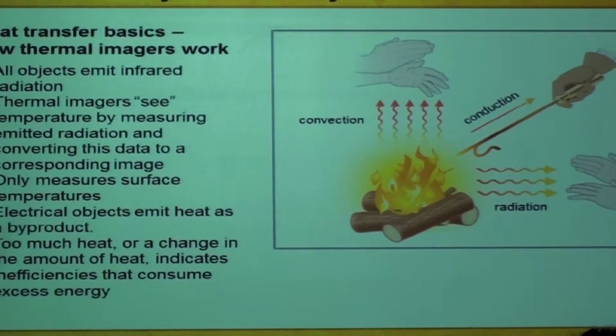So all objects will emit infrared radiation. Thermal imaging cameras are looking at this infrared radiation. They are measuring that infrared radiation, and they convert that radiation into data that you can work with. Okay? Key point to note is that we are only measuring surface temperatures. A lot of people still have the misconception that a thermal camera can look through doors. It's not possible. One of the biggest disadvantages of thermal imaging is the fact that we can't look behind closed enclosures.